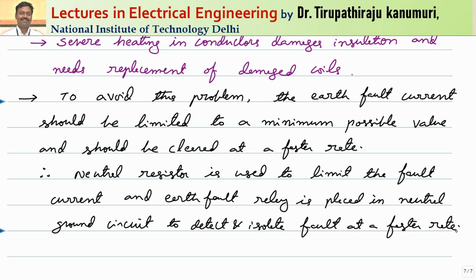The reason the alternator neutral is always connected through a resistor is to limit fault current. However, there is a disadvantage: 100 percent of the stator coil will not be protected — 10 to 20 percent of the coil near the neutral point will be unprotected. These topics will be discussed in detail in the coming lectures. I hope the different types of problems that happen in the alternator and the problems associated with them are clear. If you have any queries, you can leave your comments in the comment section below.